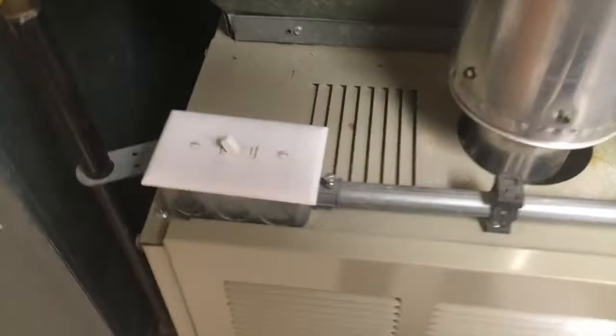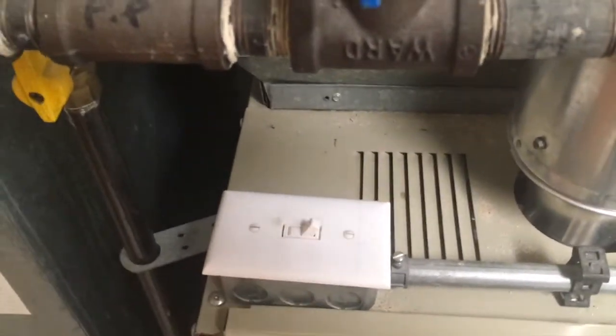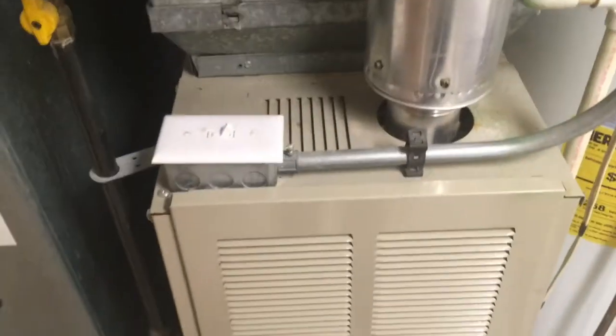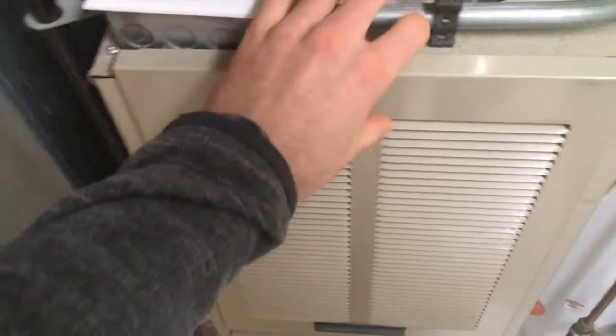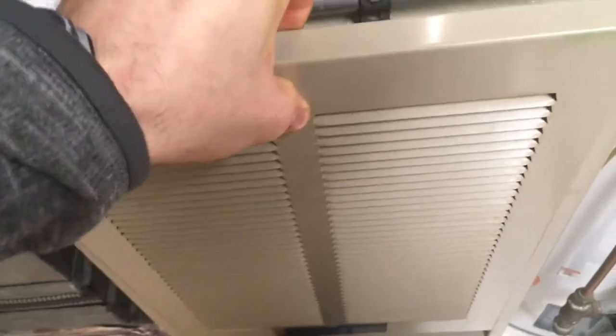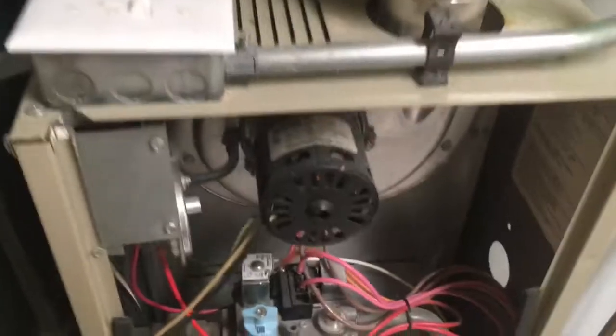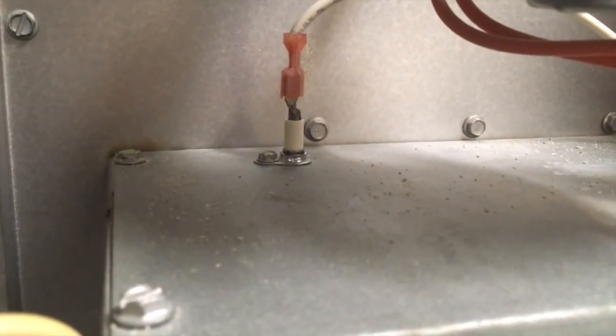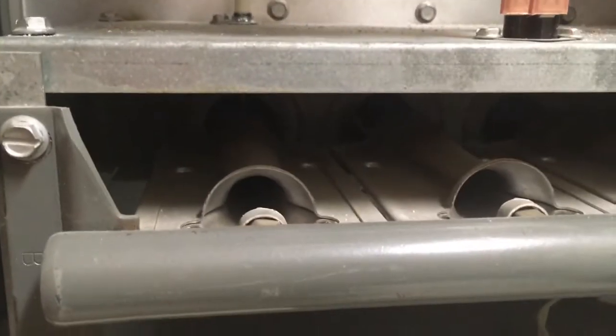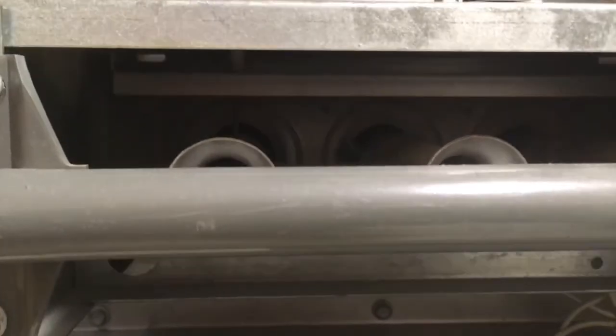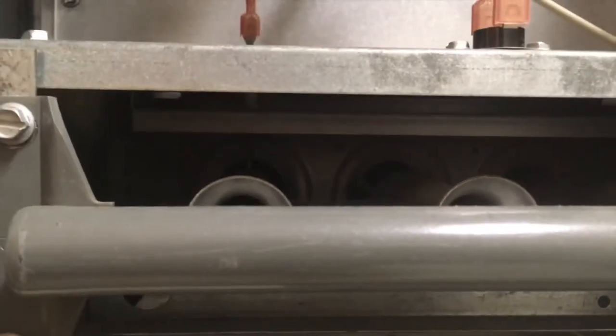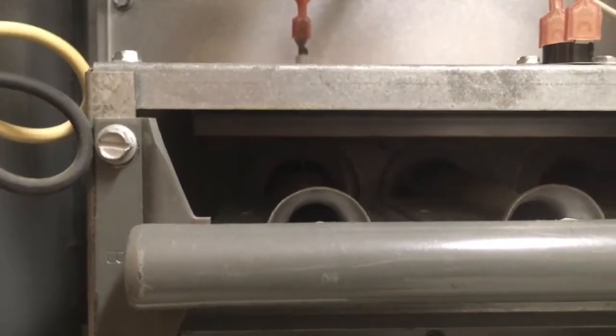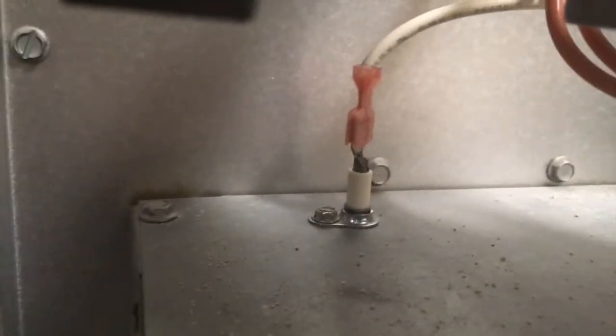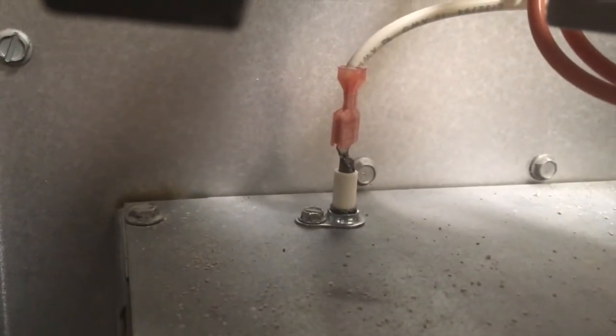First thing to do is switch the power off. Power to the furnace should be off anytime you're working on it. Then I'm going to remove the front cover. Just pull up and out. And there's your flame sensor. So if you look at the burner, the flame sensor sticks down in front of the burner. So it's that connection right back there.